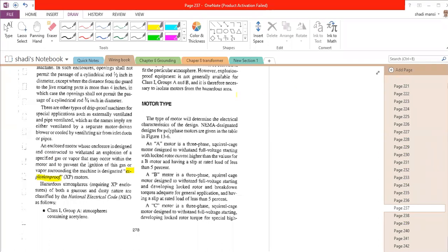اضرب لكم مثال، مثلا احنا هسه محطات البنزين، انا بدي مضخات بنزين، مضخة تشفط البنزين من التانك بتوديه على الدسبنسر والنوزل عشان نعبي فيه السيارات، صح ولا؟ فانت لما تضغط هذا النوزل الجن الفرد تبع محطة البنزين العامل بضغطه بضخ بنزين، بس في عندك مضخة. بالنسبة للي هو المواصفات السعودية، هاي تعتبر hazardous area، منطقة محطات البنزين hazardous area، فالمضخات والأجهزة الكهربائية لازم تكون explosion proof. والexplosion proof كمان له categories معين. فمضخة البنزين اللي قاعدة تشفط البنزين من التانك للمنطقة اللي انت بدك تشتغل فيها it has to be explosion proof XP. هاي اختصار كلمة XP اللي هي ايش معناتها؟ explosion proof.